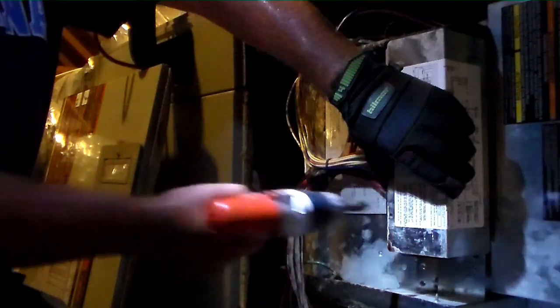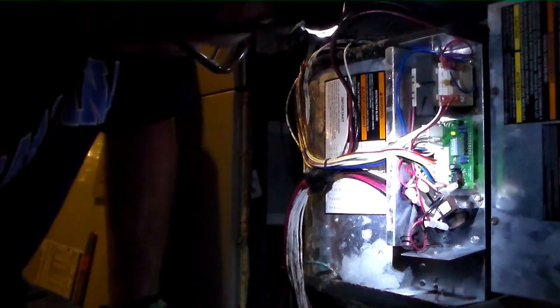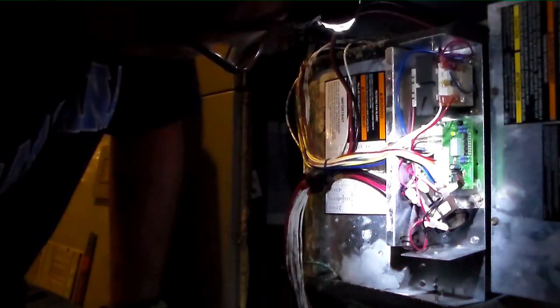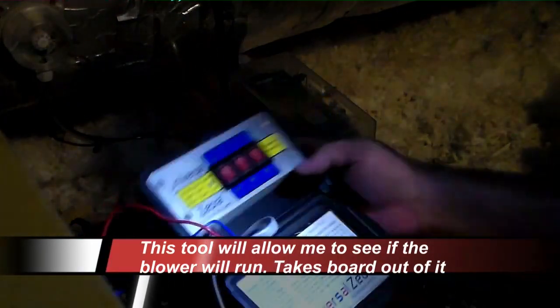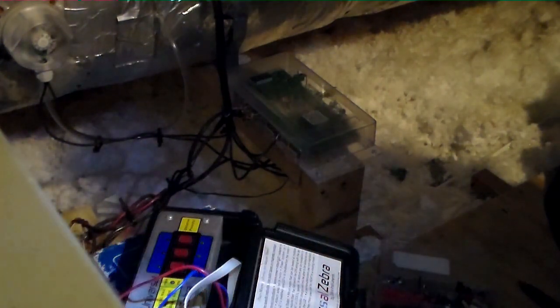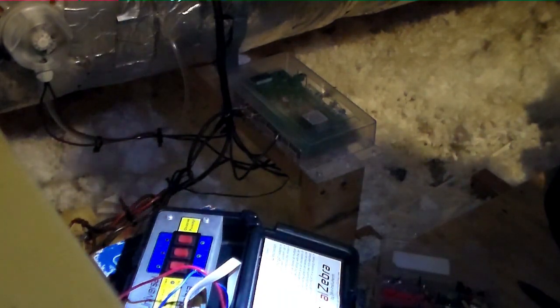Alright, let's take a closer look here. We got no CFM on the light there. What's our circuit board? We have no CFM on the light there. Let's see if we're getting a signal for the fan. Alright guys, I have my universal Zebra here, and I'm trying to operate the variable speed fan motor inside directly using these dip switches. So I'm going to turn things on at the disconnect and try to get this thing running.